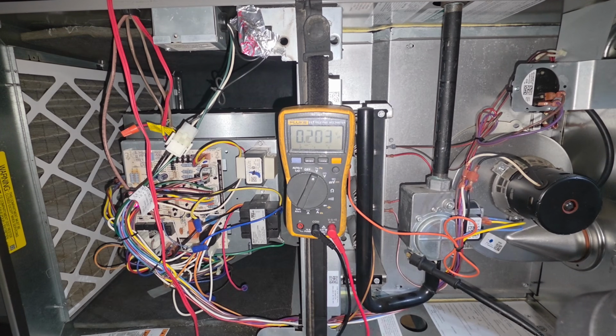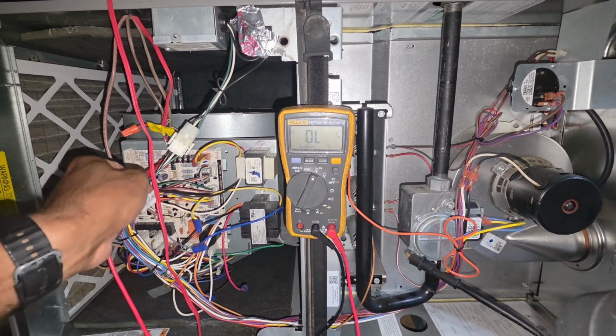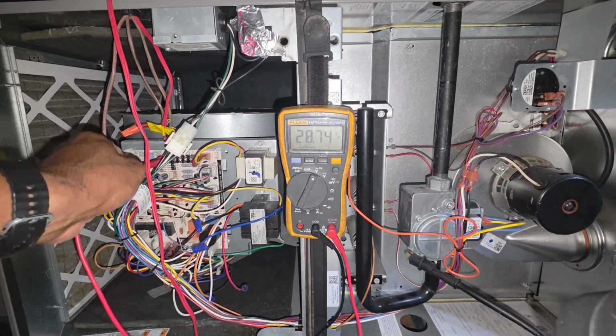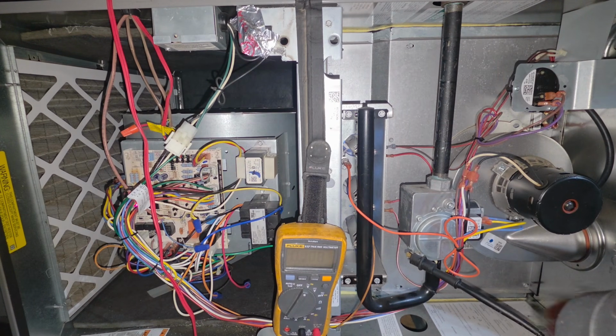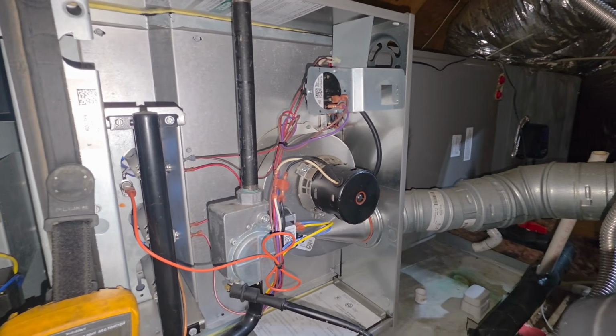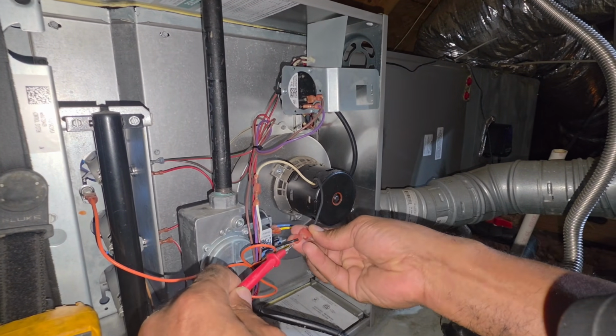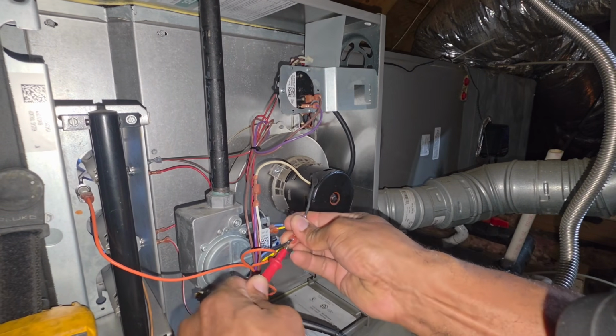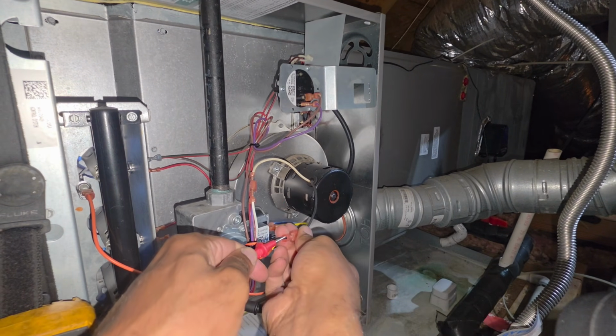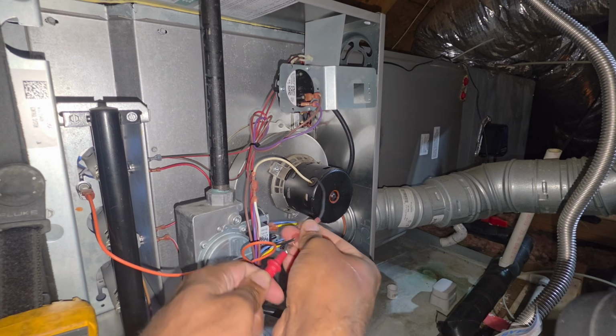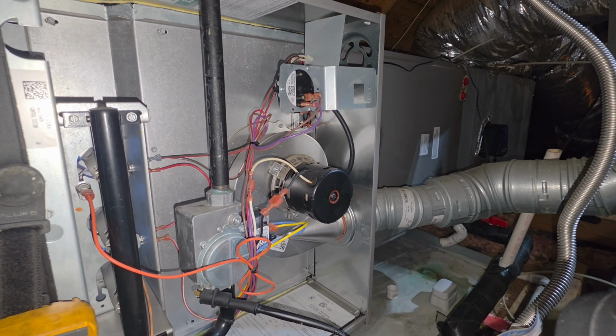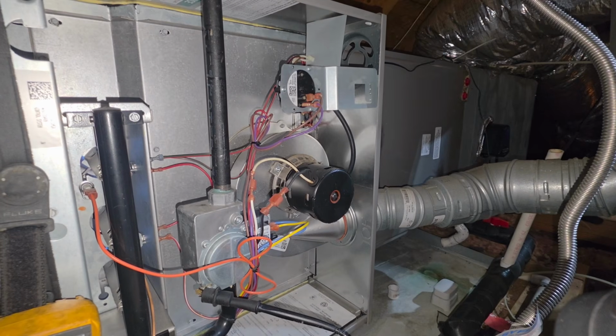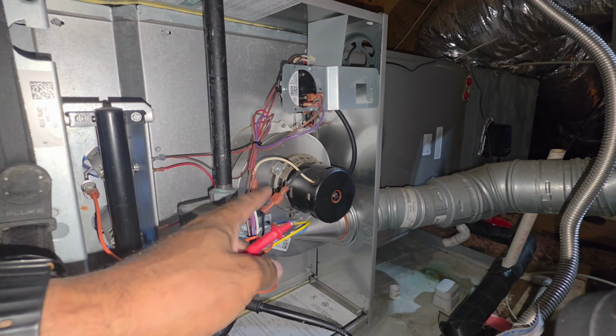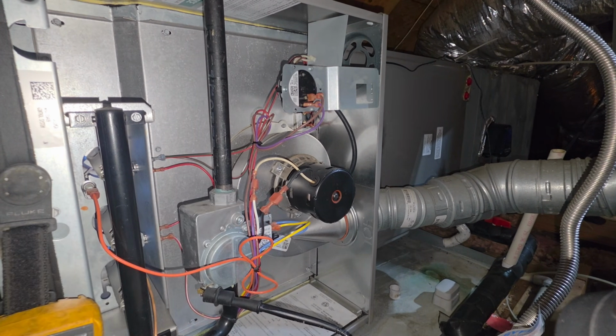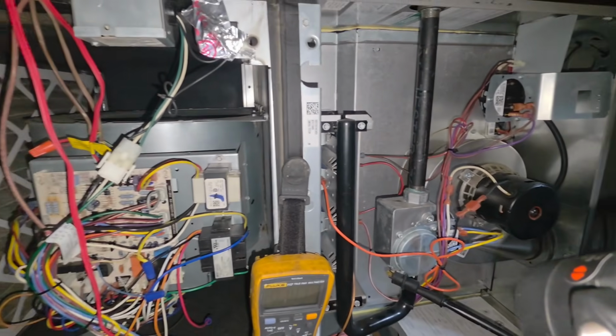And you can check low voltage like this as well. If I go to the red right here, you see I'm getting 24 volts if I go to red. But see, I got a good ground. This is my inducer fan motor right here. So if I was using the pivot method, let's see if we got voltage to that inducer fan motor. They say sometimes it's hard to get a connection. So what's easier is sometimes just go back to your control board. So let's go up to the control board and we're gonna see what kind of voltage we got at this inducer motor. Should be like 115, 120.